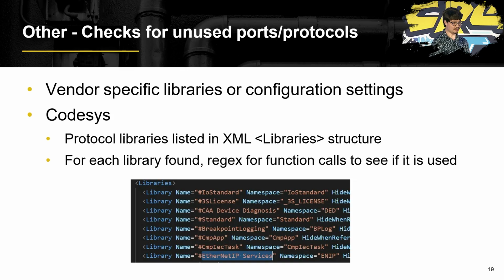Another secure PLC coding practice is checking for unused ports and protocols and not using them. So there are vendor-specific libraries and configuration settings that are often stored in an XML file. And so for this, you could simply just go through the XML file, look at the libraries that have been imported, and then check for all of the functions that that library contains. And if none of the functions are ever used, you can warn the developer they've imported a library that they don't need, and possibly they've added another unnecessary attack surface to the PLC.